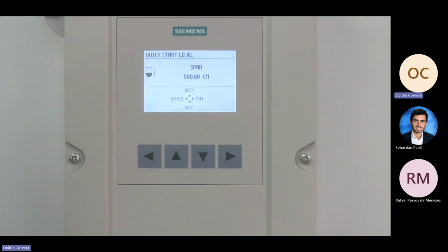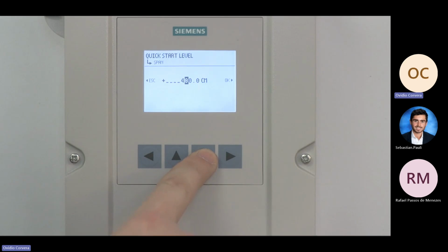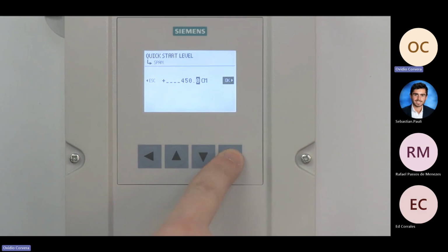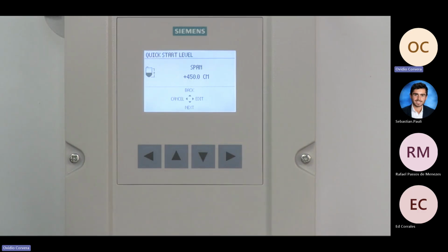The next step in the Quick Start wizard is to enter the span distance. Press the right arrow to select Edit to enter the span distance. Use the left and right arrows to move the cursor. Use the up and down arrows to increase or decrease the span distance value. The span is the measurement range from the process empty point. Once the span distance value has been entered, use the right arrow to enter the span value. To proceed, press the right arrow until OK is highlighted and press the right arrow to select. Press the down arrow to select Next to proceed to the next wizard.